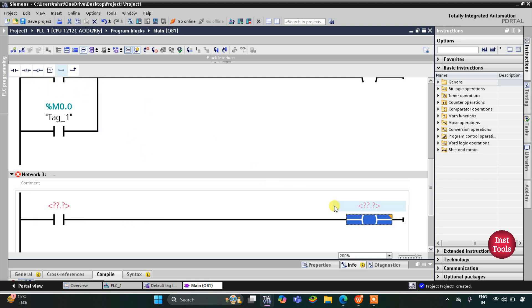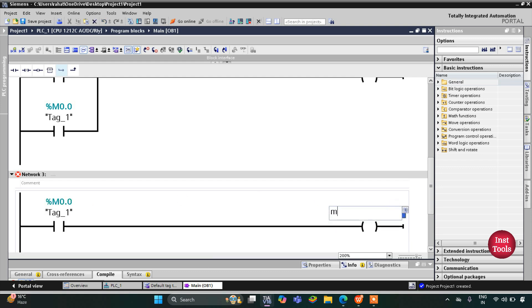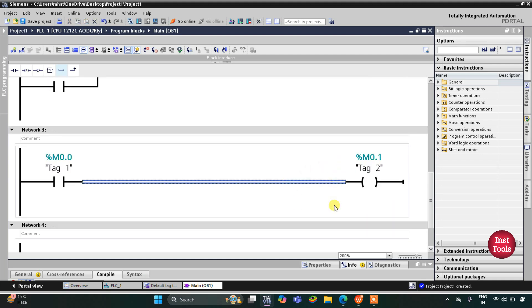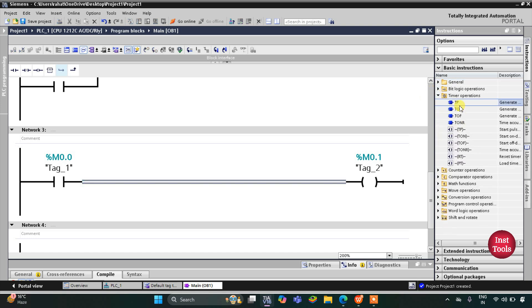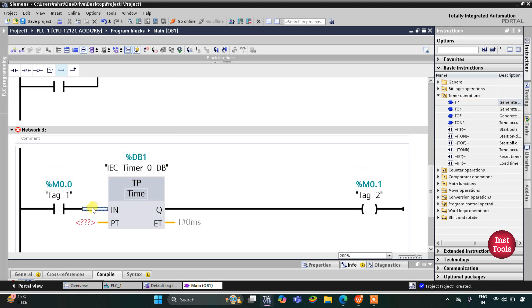When M0.0 gets set, another memory bit gets through. That memory bit M0.1 should get through for only 10 seconds, so I will use a timer operation — specifically TP (pulse timer). I will assign the address M0.0 to the input normally open contact, and M0.1 as the output. The preset value for this TP will be 10 seconds.